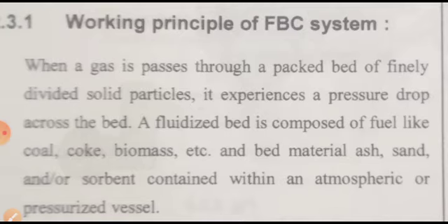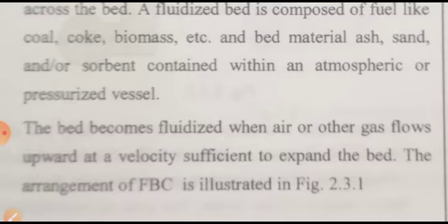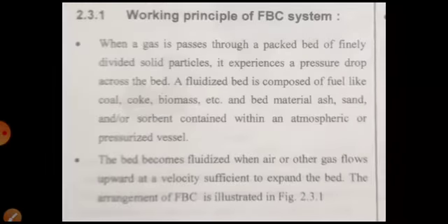When a gas is passed through a packed bed of finely divided solid particles, it experiences a pressure drop across the bed. A fluidized bed is composed of fuel like coal, coke, biomass, etc., and bed material such as ash, sand, and or sorbent contained within an atmospheric or pressurized vessel. The bed becomes fluidized when air or other gas flows upward at a velocity sufficient to expand the bed. The arrangement of FBC is illustrated in the next figure.